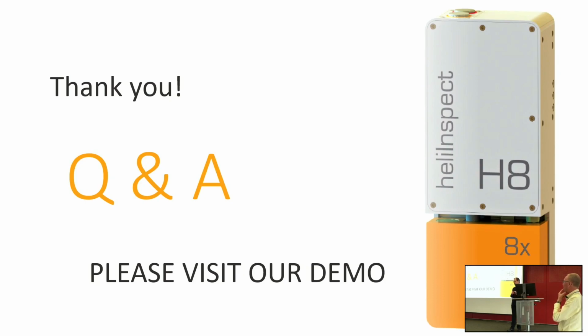So on those artifacts which I have seen, we don't really miss many points. There are a couple of outliers, but the surface is typically represented in full. Obviously, if you have now a 90 degree flank, yes, then you would miss, but pretty much no artifact has that. They are careful not to give you something like that because no other measurement device can measure that either.